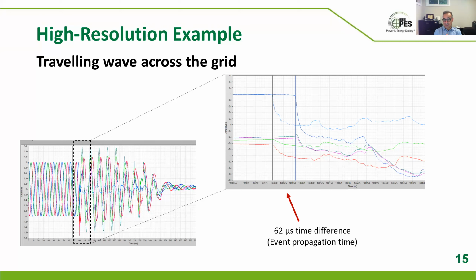But if you didn't sample at the microsecond and didn't have the bandwidth, if you sampled at 100 kilohertz, so every 10 microseconds, then you wouldn't know it within 300 meters, you would know it within 3 kilometers, which is not very nice. And even 100 kilohertz is considered fast sampling. Most relays don't do more than 10 kilohertz. And if they try traveling wave, they would show the fault within 30 kilometers. Well, that's not very useful. Many lines are not even 30 kilometers themselves, like in this case. So information like this with a regular recorder or regular relay is lost. You need something with high speed.